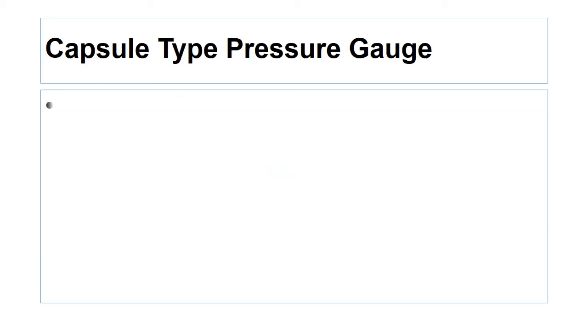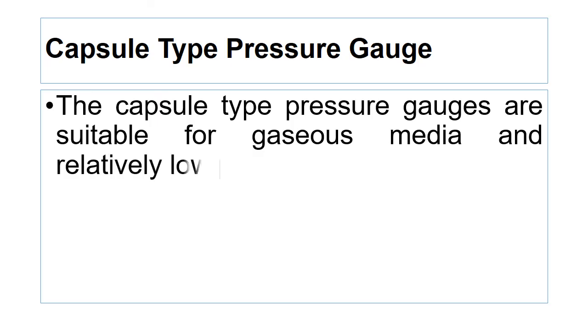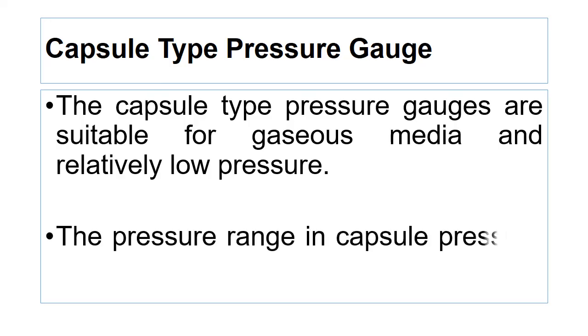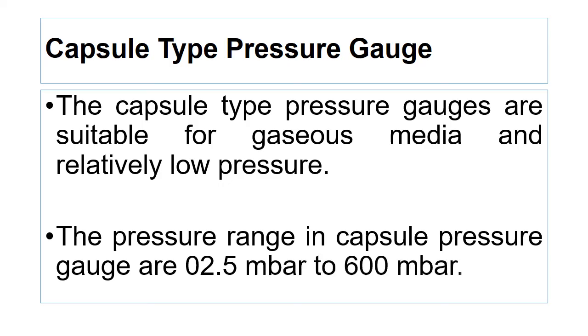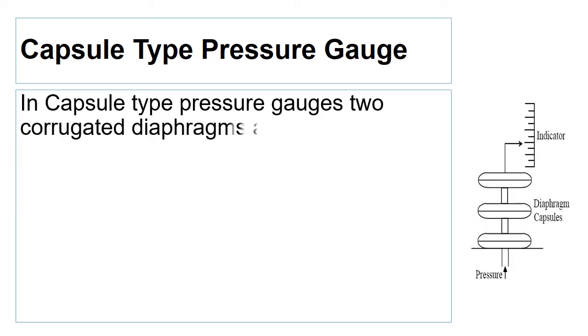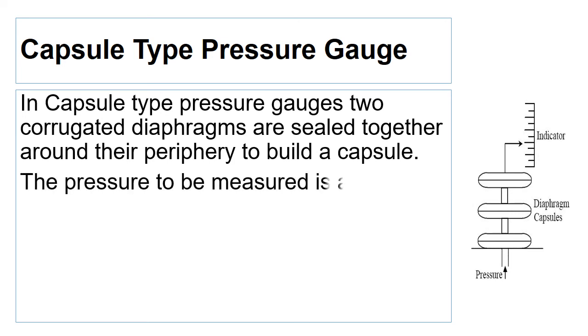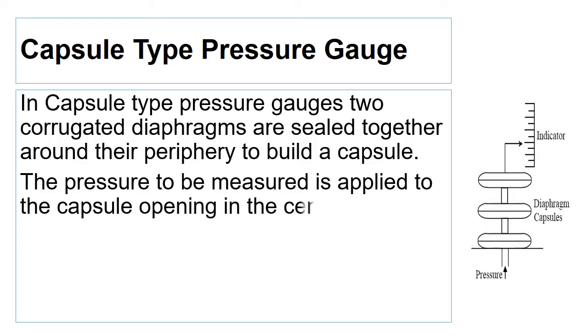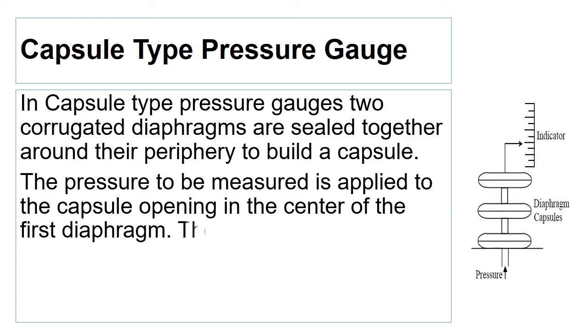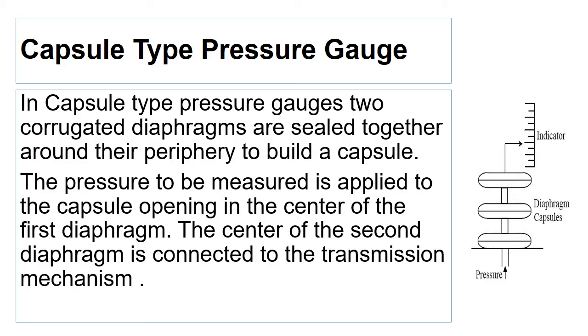The capsule type pressure gauge is suitable for gaseous media and relatively low pressure. The pressure range in capsule type pressure gauges is 2.5 millibar to 600 millibar. In capsule type pressure gauges, two corrugated diaphragms are welded together around their periphery to build a capsule. The pressure to be measured is applied to the capsule opening in the center of the first diaphragm. The center of the other diaphragm is connected to a transmission mechanism so that the deflection of the measuring element can be transmitted to the pointer.